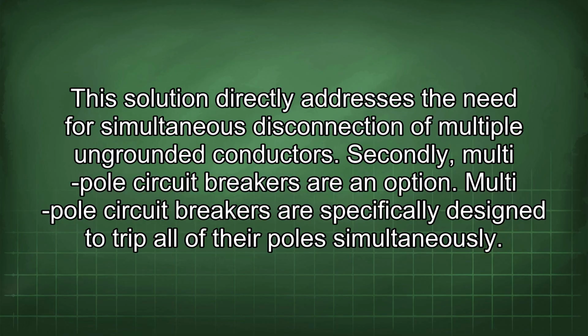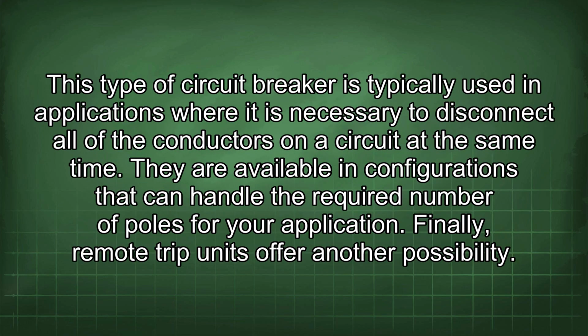Secondly, multi-pole circuit breakers are an option. Multi-pole circuit breakers are specifically designed to trip all of their poles simultaneously. This type of circuit breaker is typically used in applications where it is necessary to disconnect all of the conductors on a circuit at the same time. They are available in configurations that can handle the required number of poles for your application.